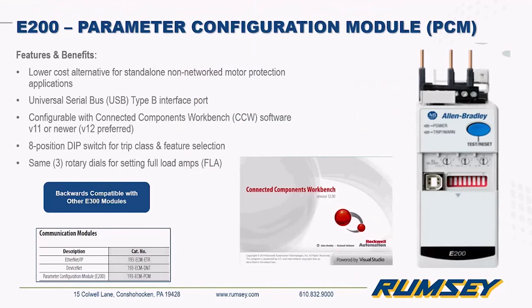Just briefly on the E200 since it's relatively new: it's nearly as powerful as the E300 but designed for non-networked applications. To access all parameters and configurations you'd use Connected Components Workbench. For a basic application you have dip switches on the front and rotary dials to set the FLA. It's also backwards compatible — if you have an E300 and want to go to a non-networked overload, you take off the communication module and put this one on.